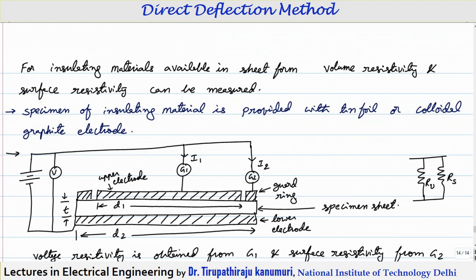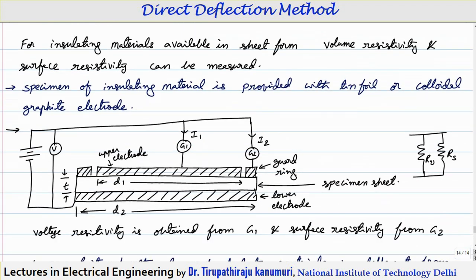For the case of insulating materials in the form of a sheet — not cables — we measure volume resistivity or surface resistivity. The specimen of the insulating material is provided with electrodes. Generally these electrodes are made using either tin foil, meaning a thin layer of tin, or colloidal graphite electrodes. A circular specimen is used, and the entire specimen is covered with an electrode on the back side — the lower side — with diameter D2.